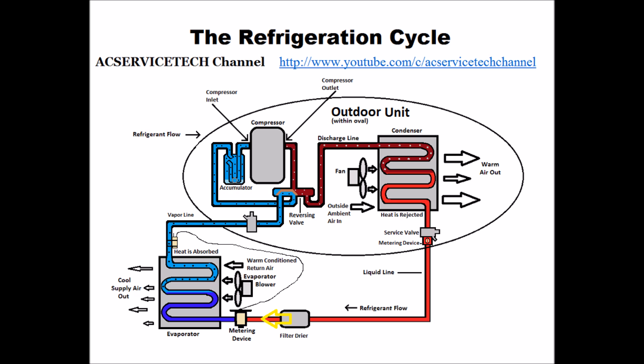In this case the metering device is a thermostatic expansion valve. The thermostatic expansion valve's job is to maintain a certain amount of superheat across the evaporator coil. Right at the metering device there is a pressure drop — it turns the high pressure, high temperature liquid refrigerant into an 80% liquid, 20% flash gas by reducing the pressure. As we know, temperature follows that pressure drop.